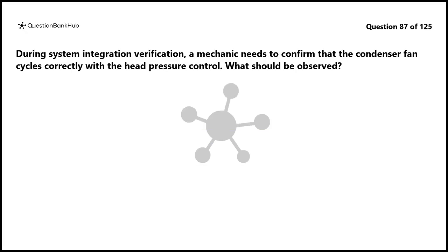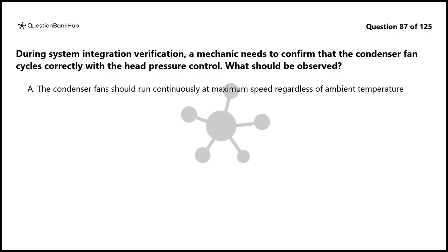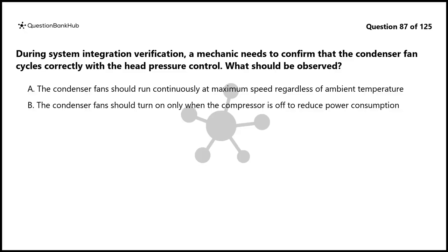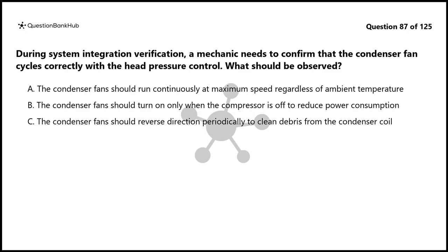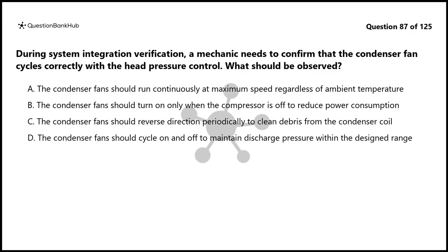Question 87. During system integration verification, a mechanic needs to confirm that the condenser fan cycles correctly with the head pressure control. What should be observed? A. The condenser fan should run continuously at maximum speed regardless of ambient temperature. B. The condenser fan should turn on only when the compressor is off to reduce power consumption. C. The condenser fan should reverse direction periodically to clean debris from the condenser coil. D. The condenser fan should cycle on and off to maintain discharge pressure within the designed range.